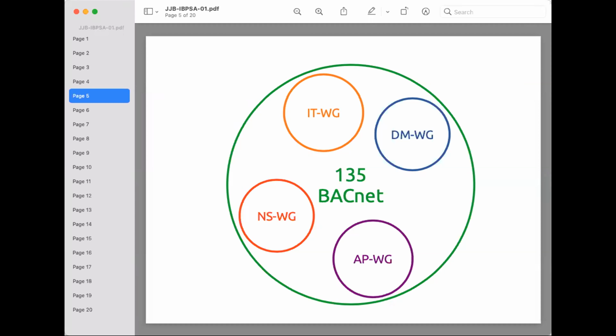So it's simple to understand what's there with respect to a device, and it's very difficult to understand what it is when examining any specific type of object. In some cases where the object names are like AV010, you needed access to, and training in, the vendor-specific device configuration to be able to understand what it is. You actually had to get into the device to understand it. Even 20 years ago, we identified this process as tedious, time-consuming, and error-prone.